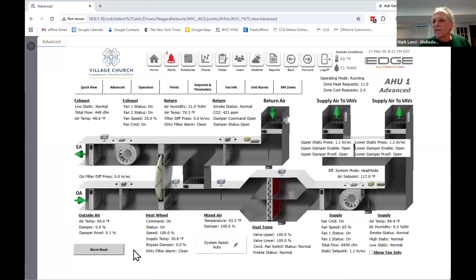So again, this is live. You see this? If there's a major trip, it looks like from what we've seen so far, I can hit this button at home and clear anything except if it's a software problem. It's like, whoops, this pump didn't pick up in time and the unit thought there wasn't enough pump pressure, so it shut itself down. Well, I can reset that with this right here.